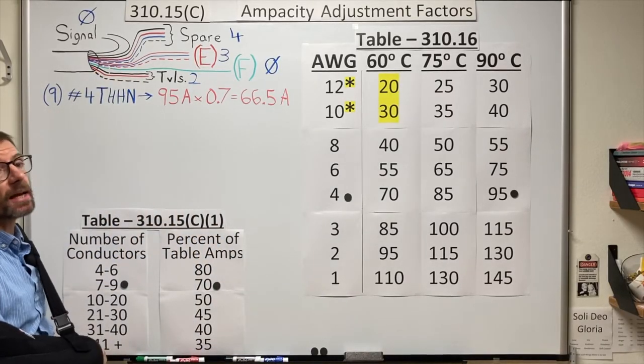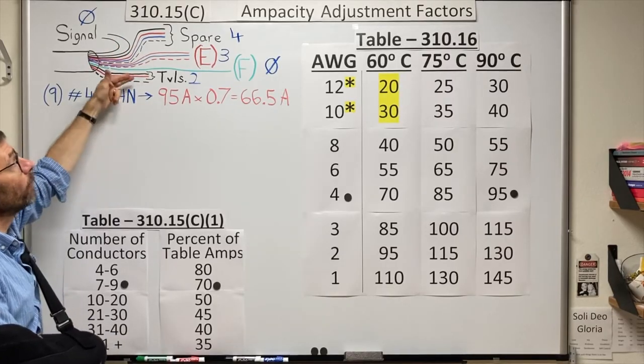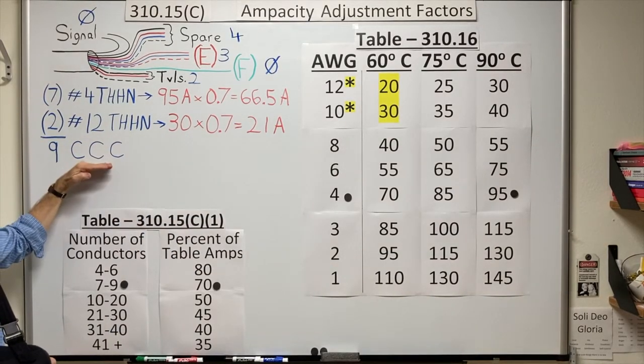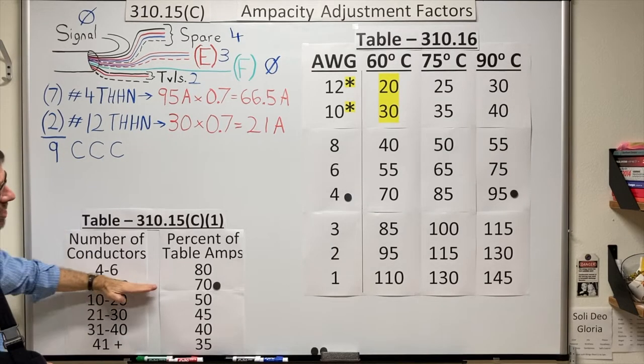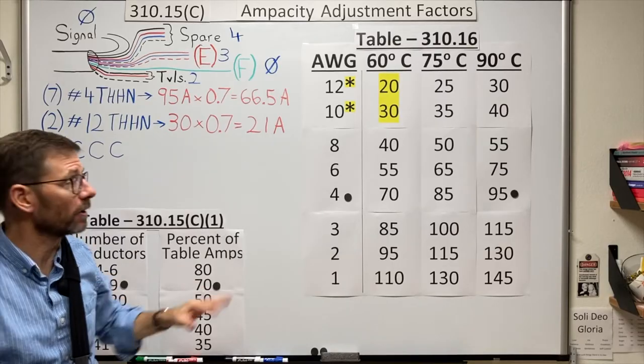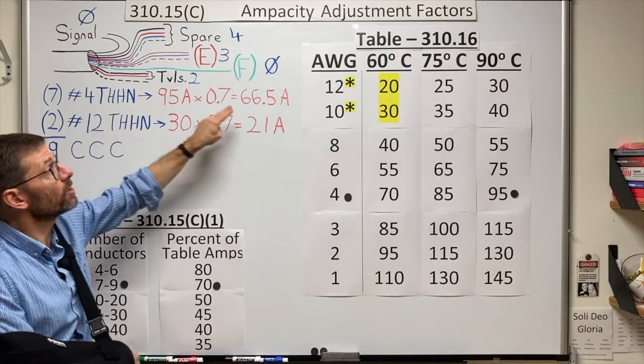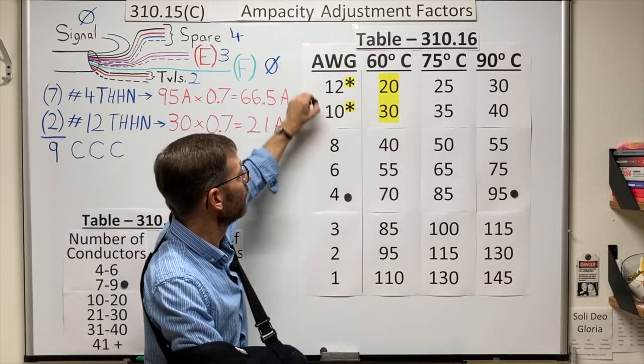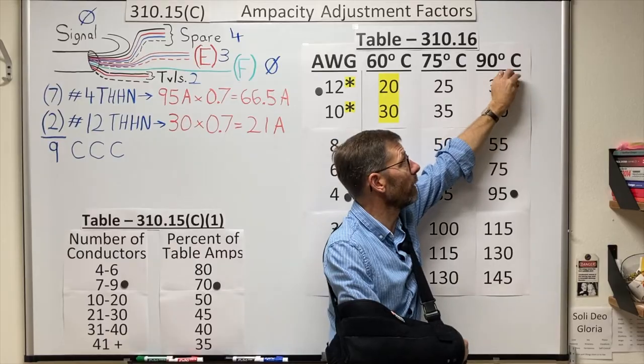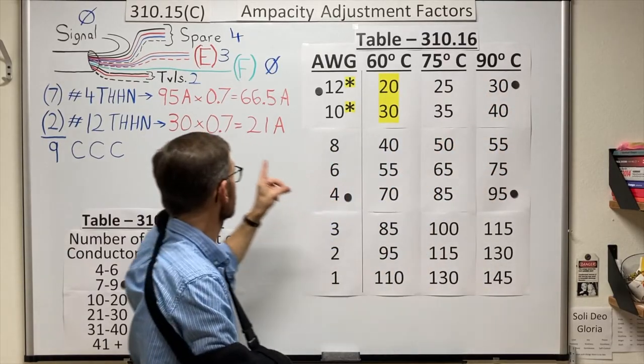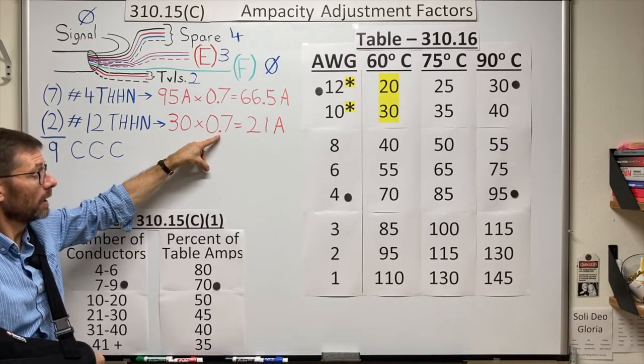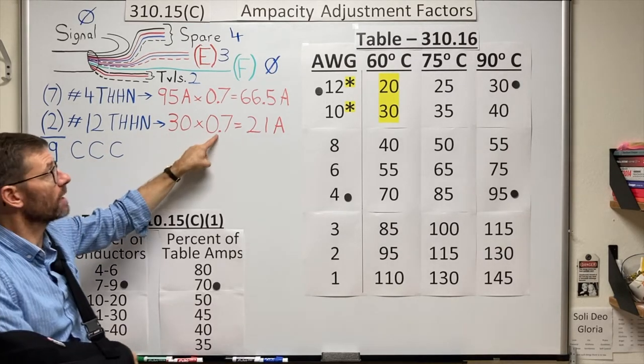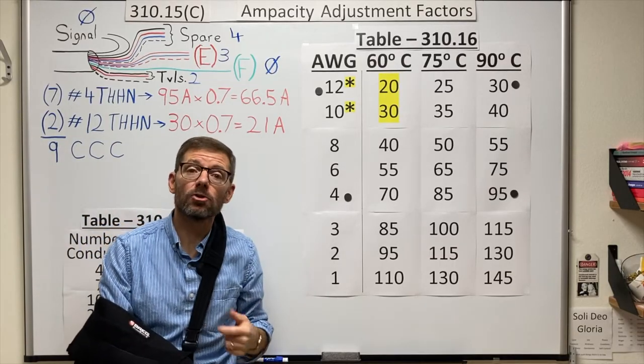But let's say not all the wires were the same size. What if some of them were number fours and some of them were number 12s? We would still have nine current carrying conductors according to our rules, and therefore we would still be limited to 70 percent of any of the conductor's original ampacities. So the number fours would still have a new ampacity of 66.5 amps. And the number 12s, let's double check on our table. The number 12 wires, still THHN, so 90 degree rating, can start their calculation at 30 amps. 30 amps times 0.7, again the factor used for the total number of current carrying conductors. 0.7 is 21 amps. Each of their new ampacities would be 21 amps.